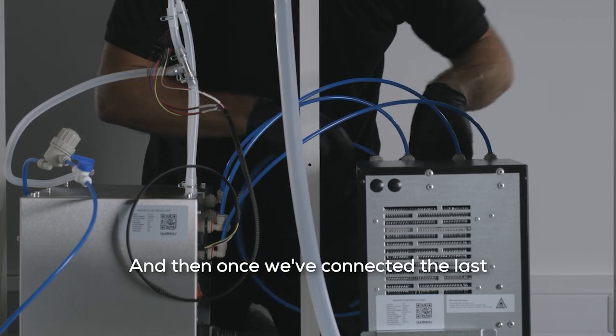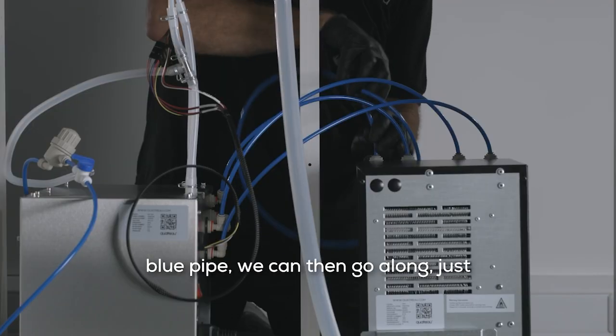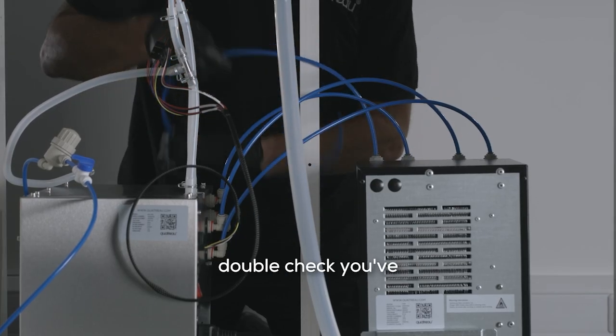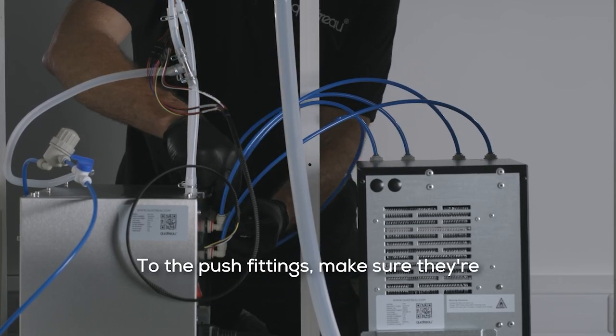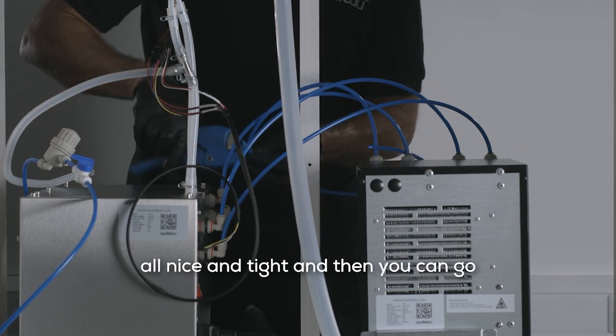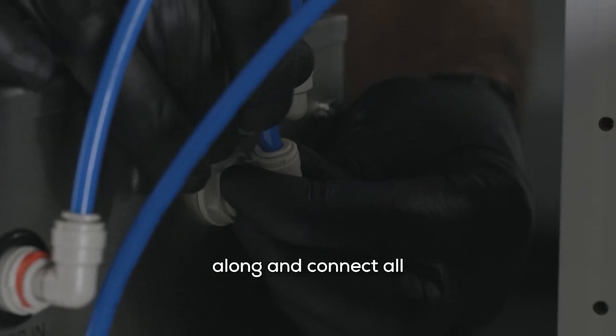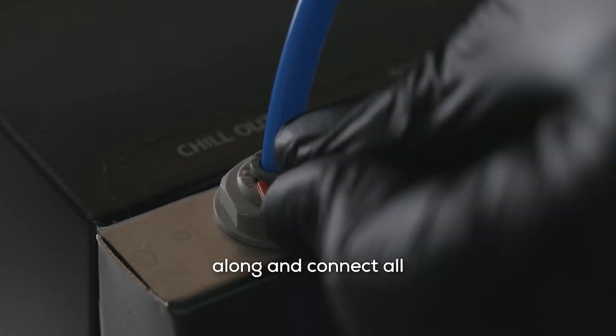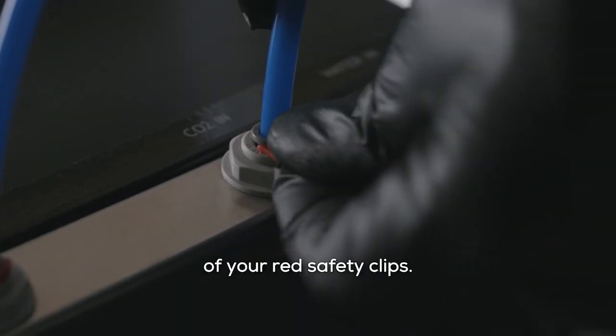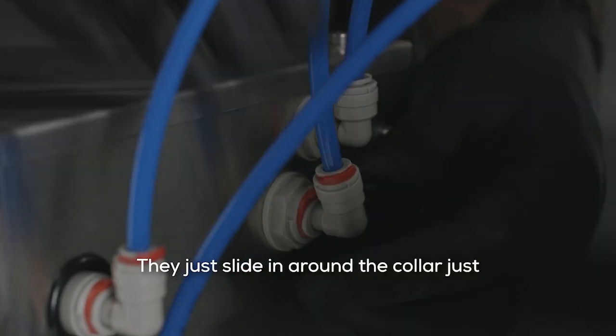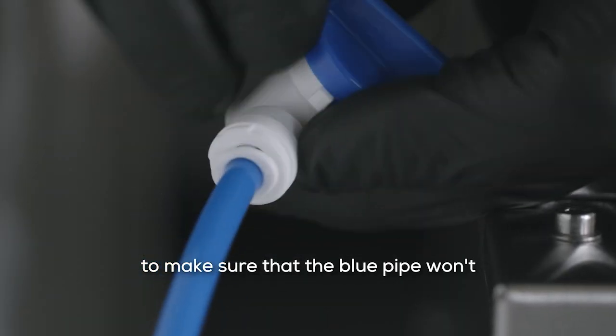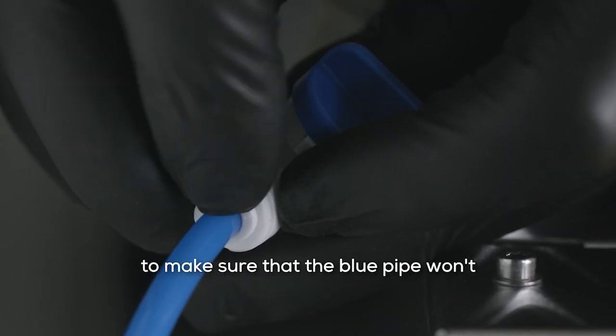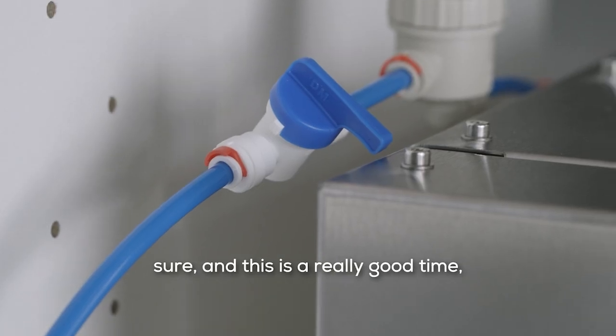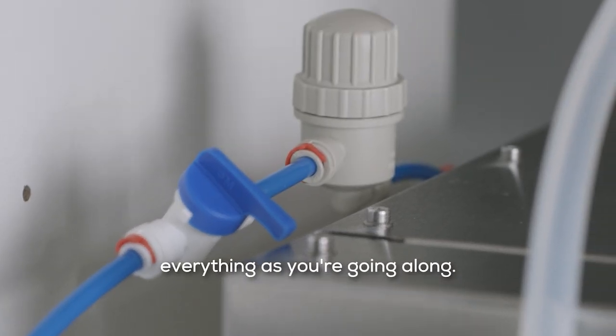And then once we've connected the last blue pipe, we can then go along, just double check you've pushed all the blue pipe in to the push fittings, make sure they're all nice and tight, and then you can go along and connect all of your red safety clips. They just slide in around the collar, just to make sure that the blue pipe won't come out if they're knocked at any point. This is quite important, and this is a really good time just to double check everything as you're going along.